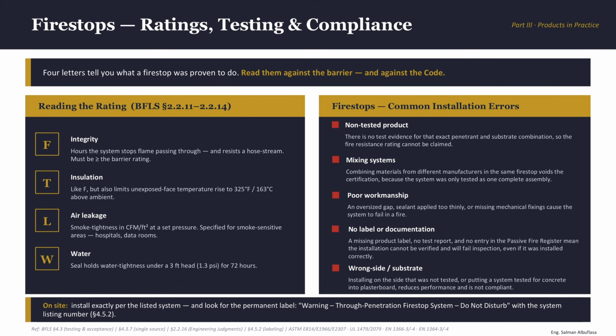Third, poor workmanship, which is basically a bad contractor. Poor installation means the fire stop was not installed correctly and will likely fail during a fire. Gaps and voids left in the opening, the wrong product used for the application, not following the manufacturer's installation instructions, and not applying enough material, so the gap will be too big. Basically, it might even look good from outside, but within, it's ineffective and will likely fail during a real fire.